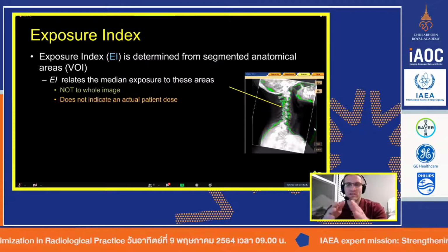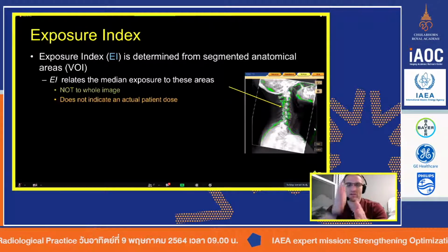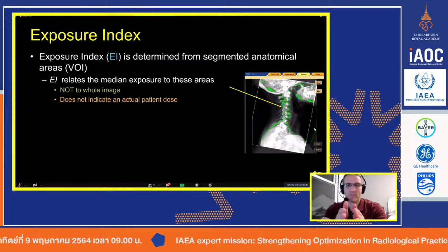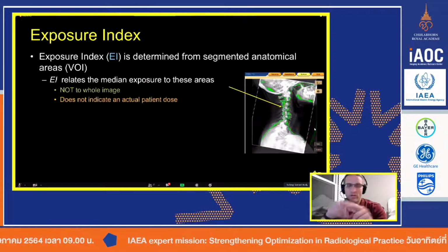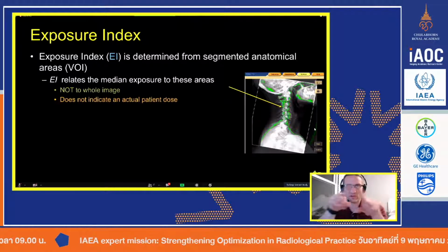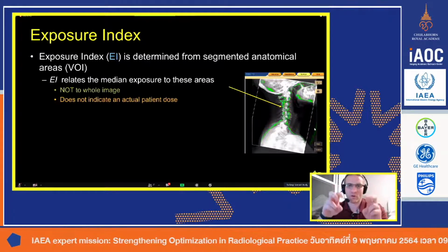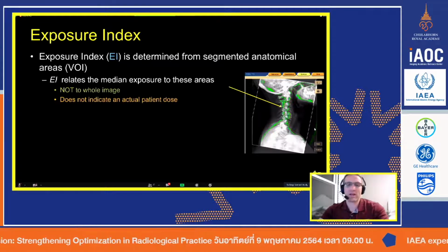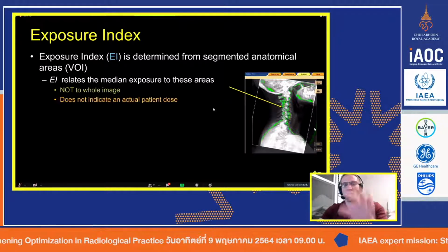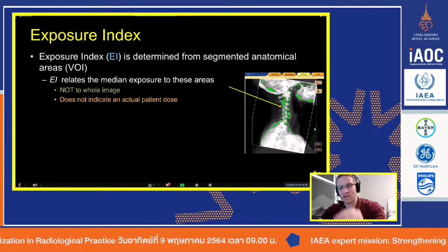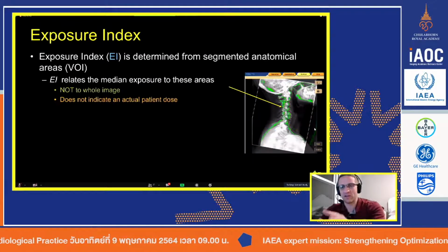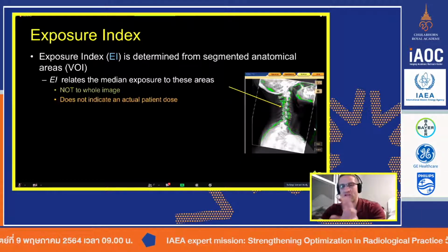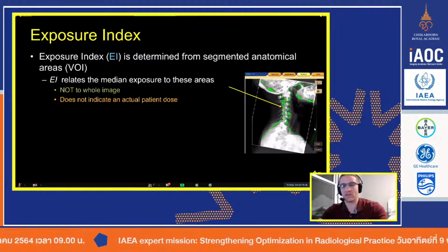And so the system knows that in that histogram, a certain amount of pixels, wherever they are in the field of view, the 2D image, correlate to that type of anatomy, in this case, bony anatomy. So the system can figure out where the dose is behind this anatomy, which is depicted here using these green pixels. That's just telling you where the system is calculating the EI.